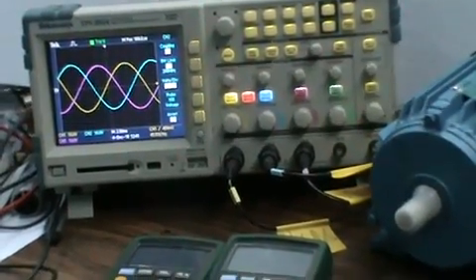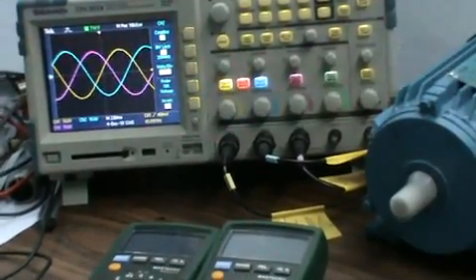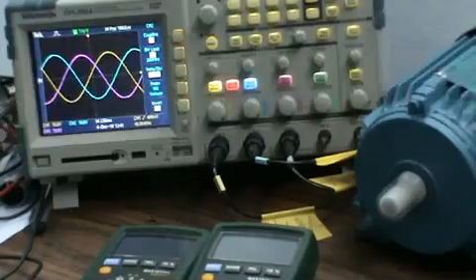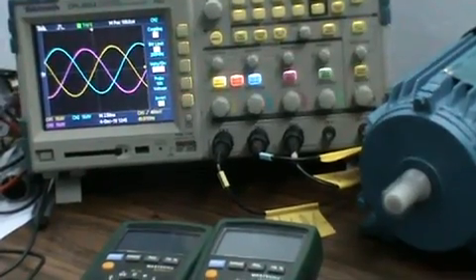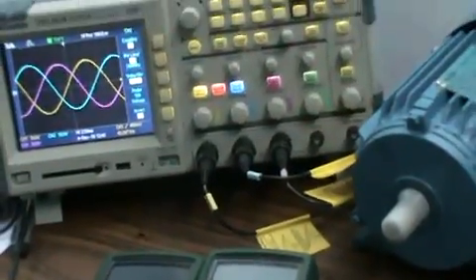Now the frequency has reached the normal 50 Hz and the motor speed has reached 1390 rpm. This is the rated motor speed. If you connect this motor directly to the main supply, the motor will run at this speed only.